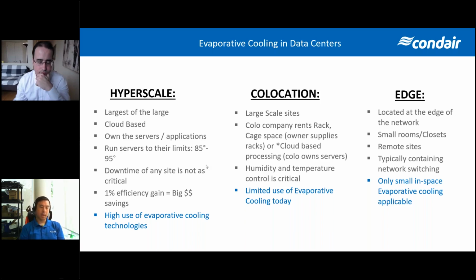In terms of data centers, on the colo side, we do see the use of evaporative cooling as well. It is fairly limited depending on which colo provider we're talking about. Typically, evaporative cooling systems are going to be used on the larger scale sites where they can really take advantage of the scalability and the cooling effects there. On the edge side, these are typically smaller facilities, small rooms or closets, and just based on the load and the requirement for cooling and humidification, we don't really see a lot of evaporative cooling being used there. So on the data center side, primarily hyperscale and co-location facilities are really where we're seeing the expanse in terms of evaporative cooling systems being used.